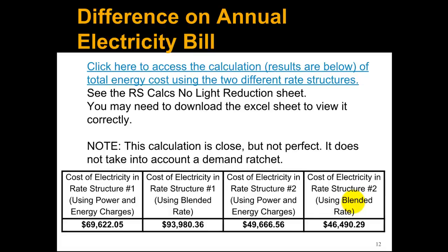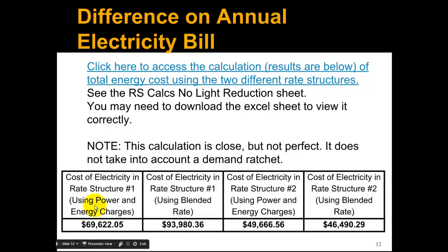If we just look at the cost of electricity — I had the 15-minute consumption data of the school — I used that to calculate the cost of electricity in rate structure number one. If I do it using the energy and power charges, which is the correct way, I get $69,000. If I use the blended rate, I get $93,000. That's a huge difference, and that's why we really want to use the power and energy charges and not the blended rate.